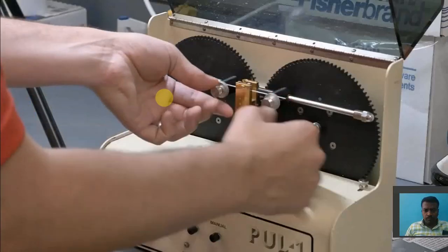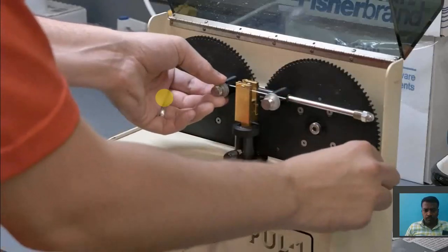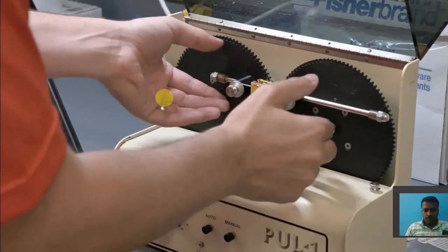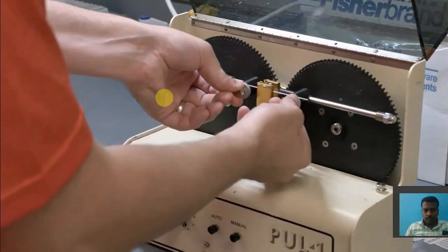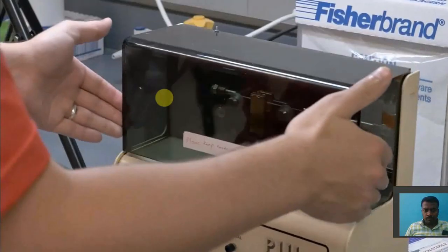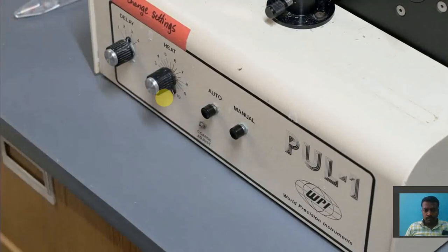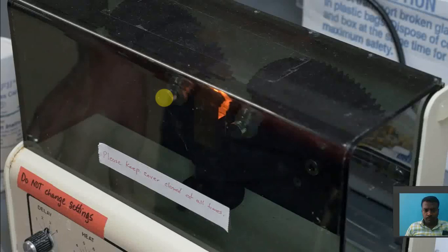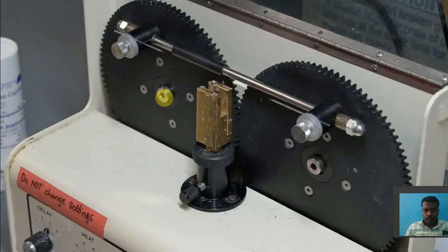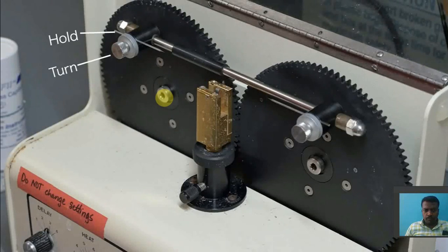They cannot be too tight. Release the brake while holding one of the knobs. Make sure the wheels cannot slip. Close the electrode puller. Use the auto button to turn on the heating element. It should take approximately 7 seconds to pull the electrodes. When the heating element shuts off, open the lid. Two electrodes are now ready. Loosen the knob while holding the outside of the electrode to remove each one.